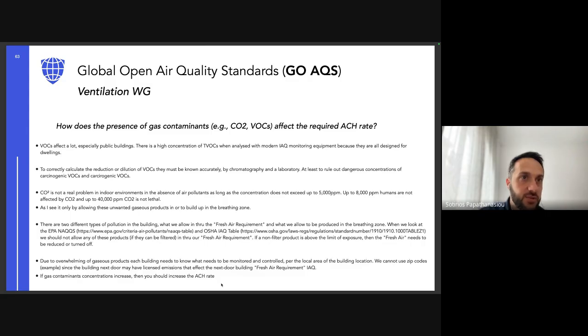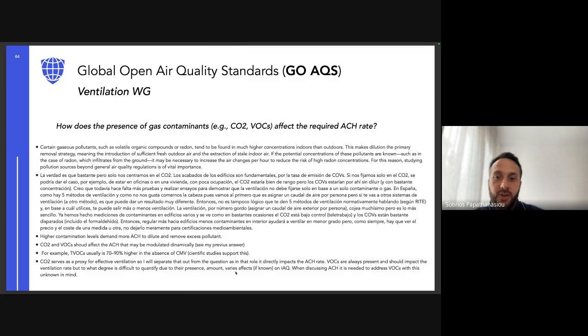If gas contaminant concentration increases, then you should increase the air exchange rates. This is a little tricky, though, as we need to know where the gases are coming from. If VOCs are coming from outdoors, increasing the ventilation rates may introduce more VOCs inside the building, or other pollutants like nitrogen dioxide. I hope everyone agrees on that. I would really like to hear your opinion today.